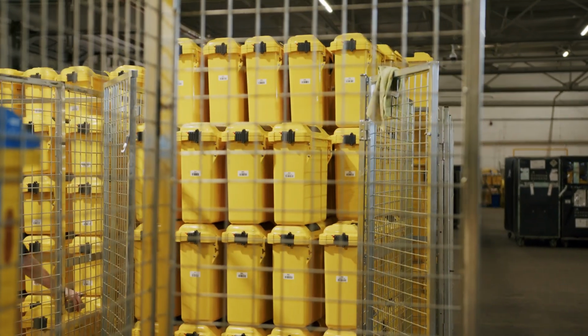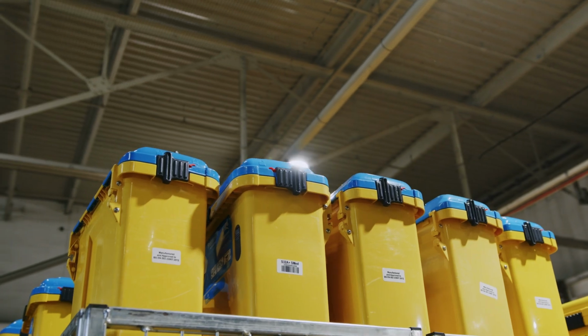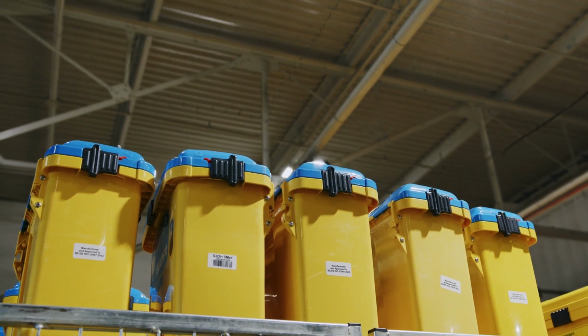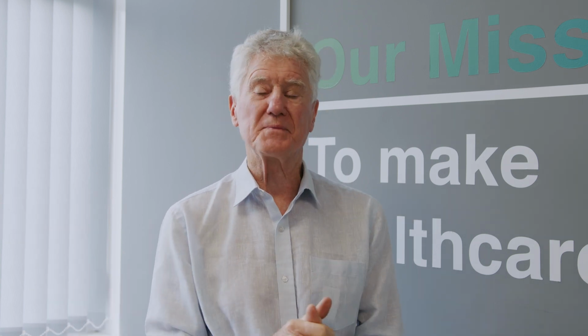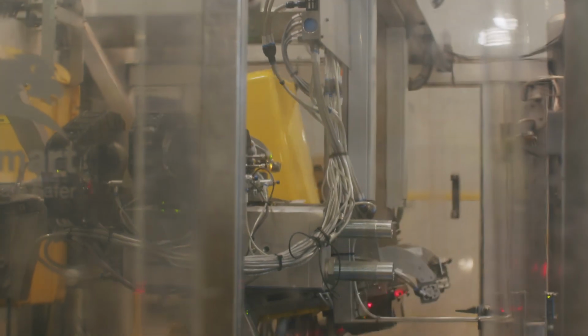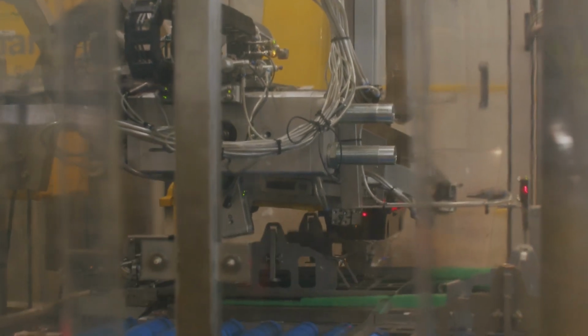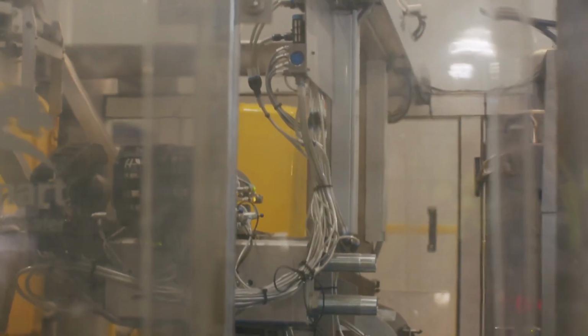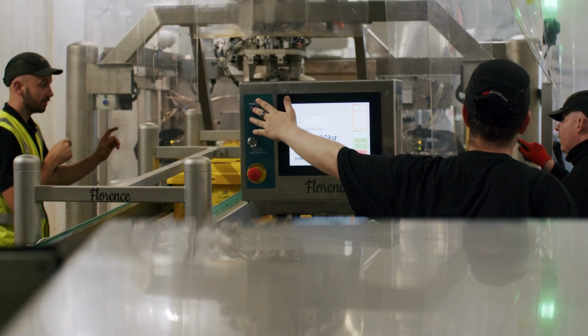But once you get to high-level disinfection, which is the level that we go to for heat labile endoscopes, you know, those scopes that you might put into lungs or knees in particular, the heat labile ones that can't be autoclaved, that definition is 6 logs of vegetative organisms. And the people I'm talking to will know about vegetative. They're not spores, they're the ones that continue to grow without forming little spores of themselves and surviving harsh environments. So you're talking 6 logs of vegetative organisms for high-level disinfection. Now that's high level. That's the top. And you know, a lot of people will accept that as sterilization.